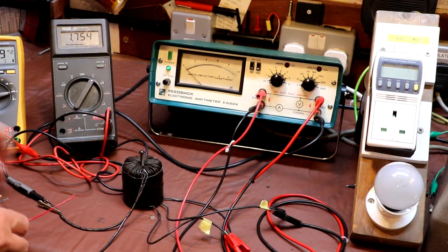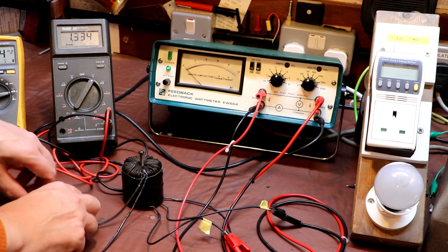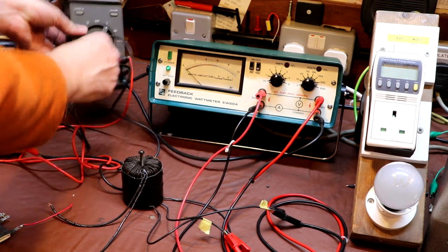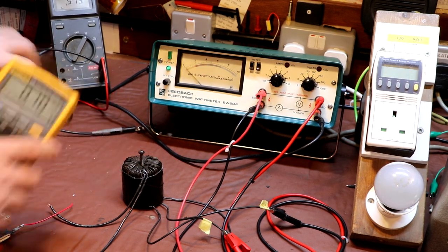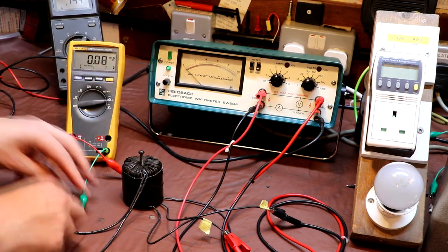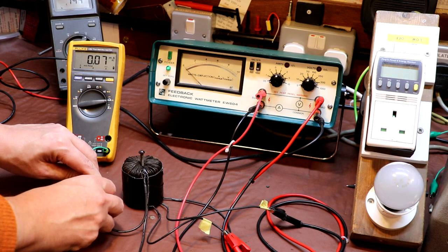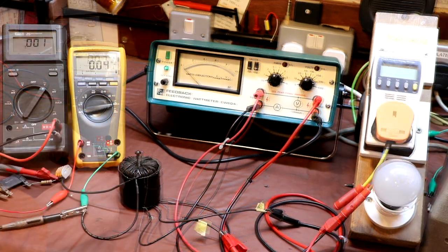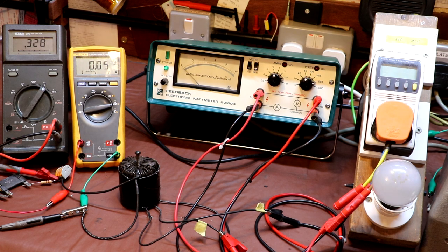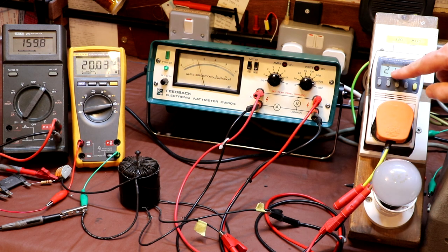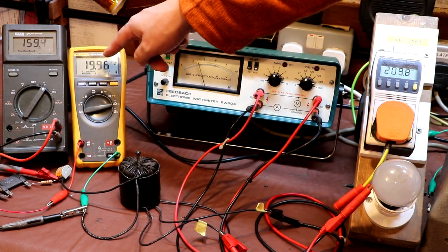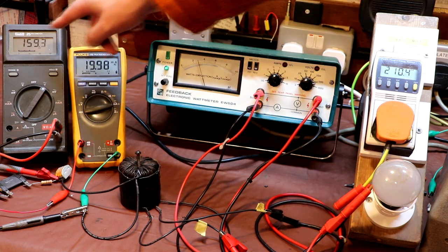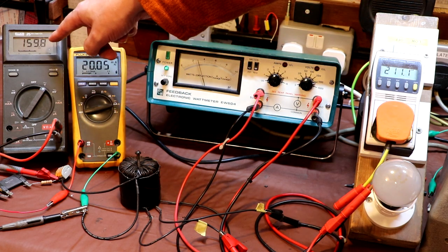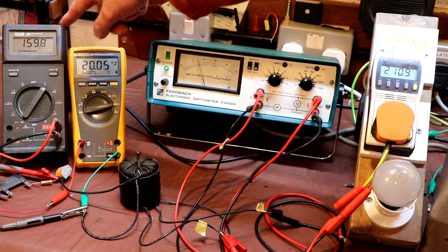What I'm going to do next is install our load, but I'm going to connect our load via a milliamp meter so we can see what that load is. So I'm going to put the ammeter there. Now, I know I've got the watt meter on the bench at the moment, but that isn't used for this test, it just happens to still be here. So let's switch on, and I'm going to wind up the voltage until we've got 210 volts on the primary. Okay, so we've got 210 volts on the primary. We can see our ammeter here is drawing a 20 milliamp load from the transformer, and our loaded secondary voltage is now 159 volts. So you need to write that down, 159 volts.